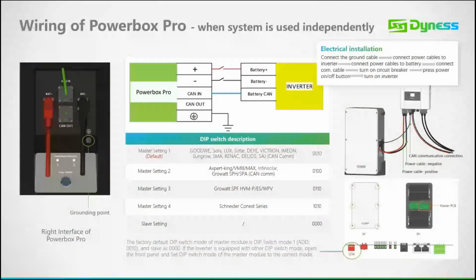Wiring of your Powerbox Pro. So this wiring is when using one battery. So the electrical installation wiring is: connect the ground cable, connect power cables to inverter, connect power cables to battery, connect your communication cable, turn on circuit breaker, press power on and off switch for approximately 3 seconds, and your inverter will then turn on.